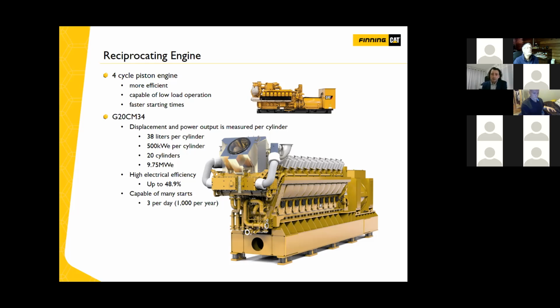It's capable of many starts, about 3 starts per day, 1,000 starts per year, which is one reason it's great for peaking applications as well as combined heat and power. To give you an idea, we're supplying one of these engines to a site that's also going to have Caterpillar turbines. They'll use the turbines for CHP application because they need steam—it's an industrial site, but they still wanted a reciprocating style engine because they recognized the high electrical efficiency it brings to the table.